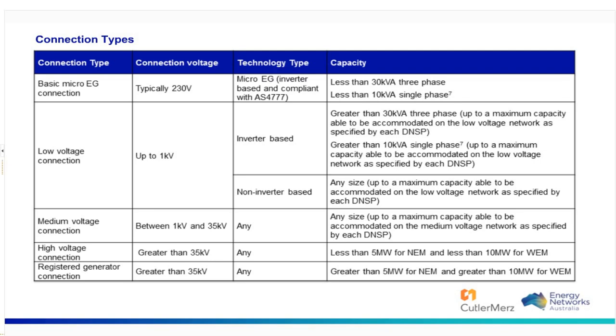Now, AS4777 does extend to 200 kVA, but the basic micro-embedded generation connection defined in this guideline only goes up to 30 kVA for a 3-phase connection. We have also specified a 10 kVA single-phase connection.